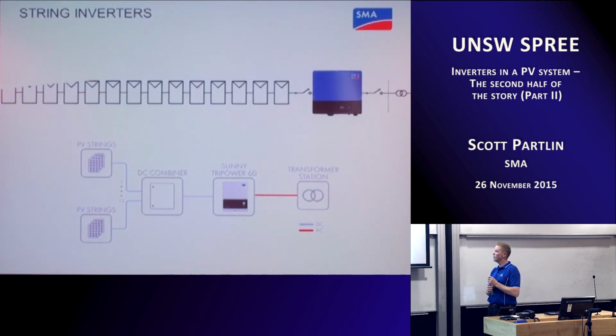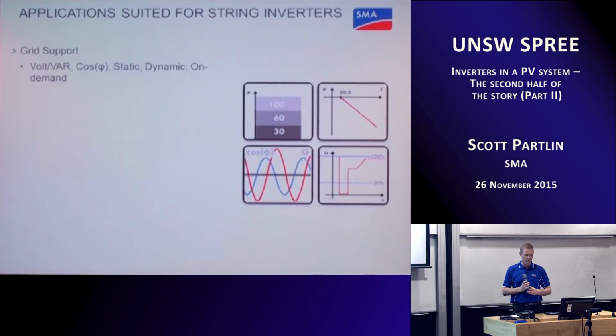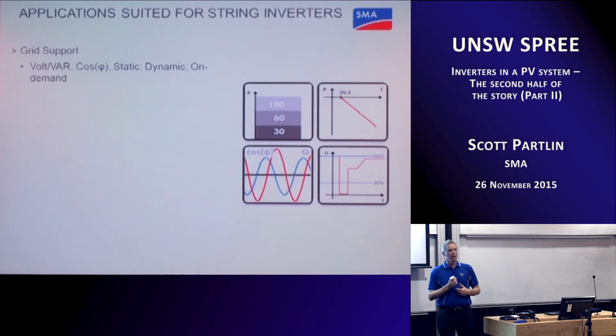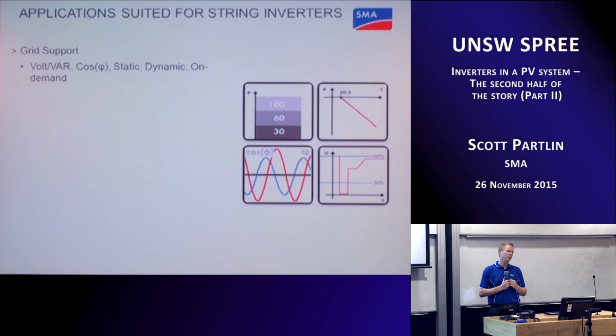String inverters. So what have we got with string inverters? What applications are they best suited for? If you have to provide grid support, if you have to provide on-demand active power curtailment because the utility has stipulated you shall, if you need to provide frequency support in terms of reducing the output power of the inverter according to the grid's operating frequency, if you need to provide reactive power support to help reduce line voltage or fault ride through under short circuit conditions or fault conditions on the network, if those are things which the application requires, then the best solution is going to be a string inverter, not least of all because microinverters aren't able to provide that same level of grid support.